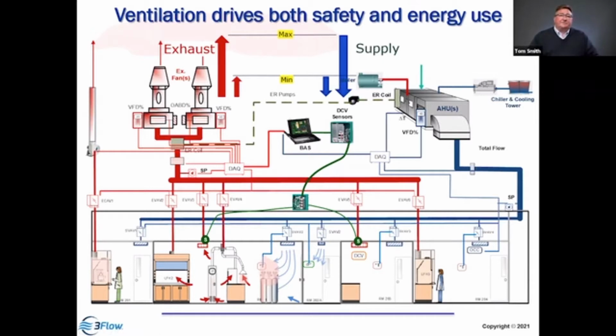Now, oftentimes you want to run the building at a little bit positive pressure, so you're going to run a little bit more supply than exhaust. But as you open and close the fume hoods, that flow through the fume hood is going to modulate. That's a modern control. We also want the exhaust and the air supply to modulate in tandem so that they're providing a balanced system regardless of the operating mode, whether you're at low flow or high flow, they're in balance. And that means all of these parts and pieces have to work properly. Now, as the flow goes, so does the energy. Labs are very expensive. They consume a lot of energy, and the bulk of it is right in the HVAC system.